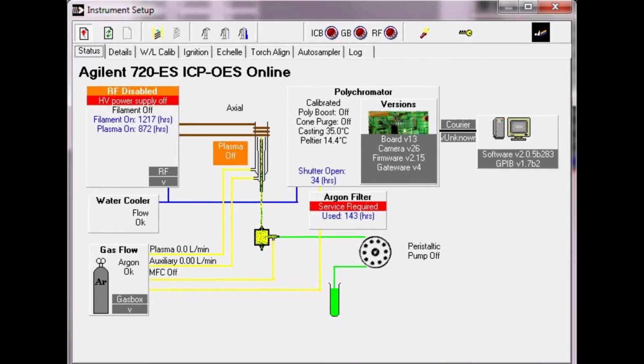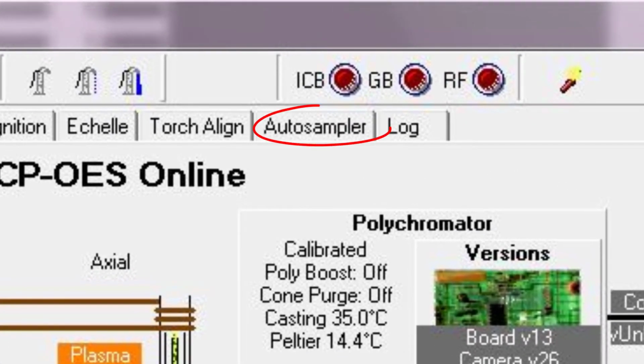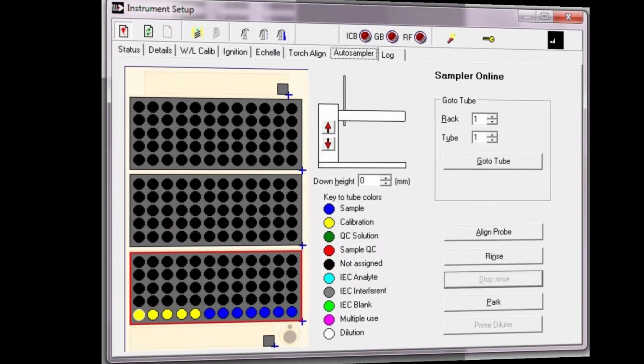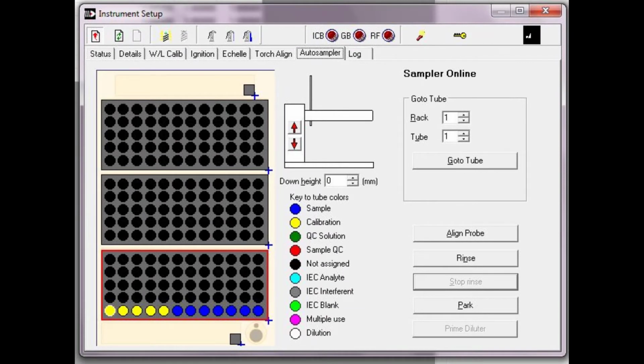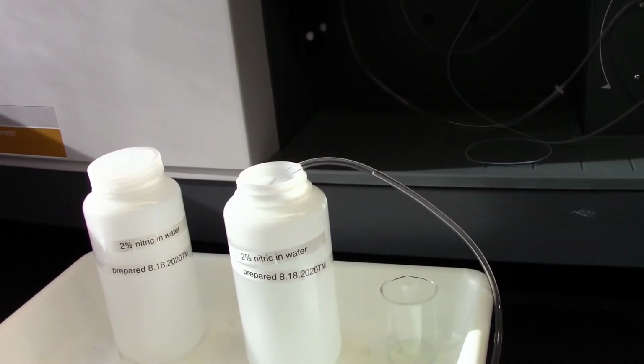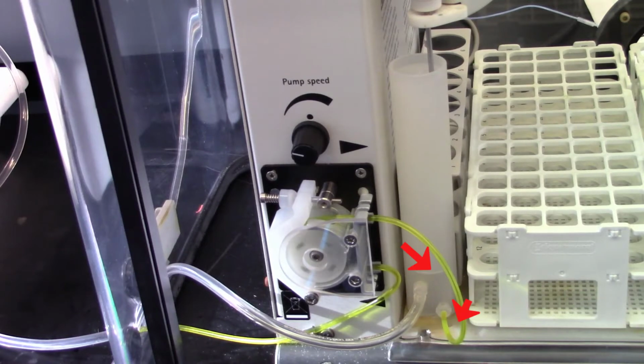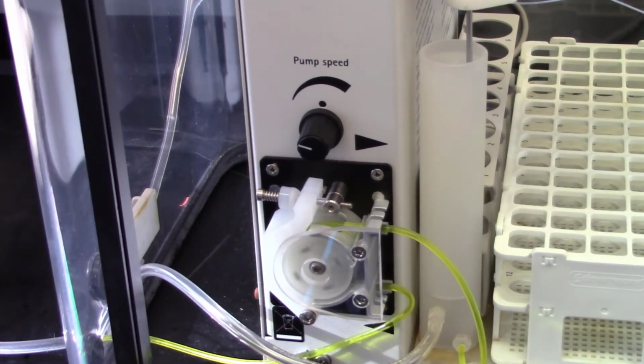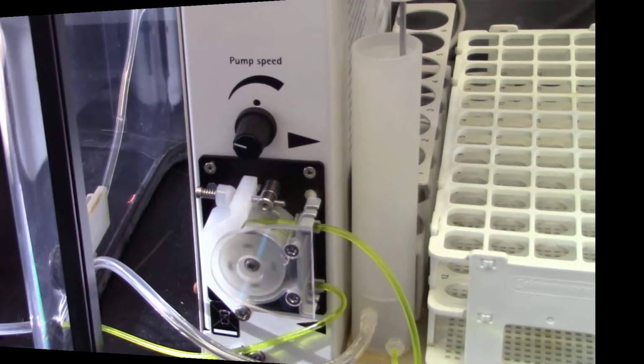For now, everything looks great, so we can open the Auto Sampler tab, which will look familiar to you. To flush the system with the wash solution, click on Rinse, and then the Pump Fast icon. Watch what is happening with the tubing. The pumps will first start drawing the nitric acid solution and feeding the auto sampler. Be sure that the liquid goes up the rinse tube and down to the waste. It rarely clogs, but if it overflows, you'll need to be sure to keep an eye on it.